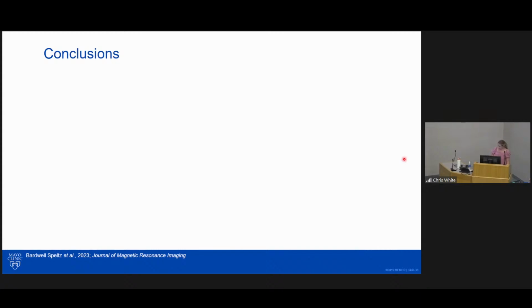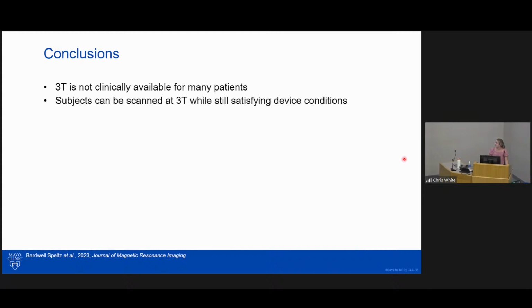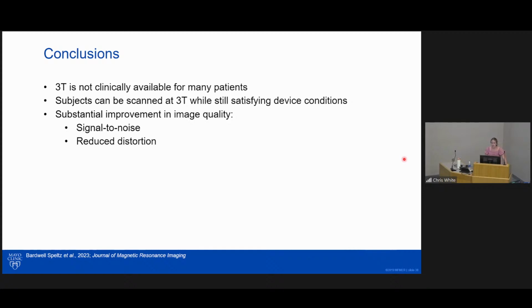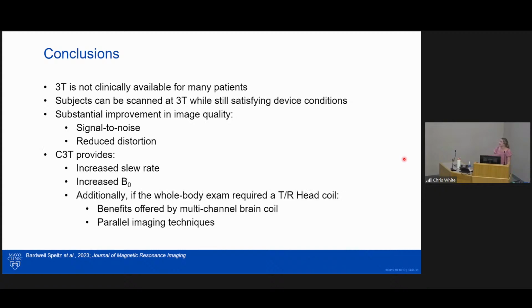So then conclusions. 3T imaging has become the clinical standard for brain imaging, but it is not clinically available for many patients with implanted devices due to MR safety concerns. This study demonstrates how subjects with implanted devices or abandoned CIED leads can be scanned at 3T while still satisfying the device conditions. Compared to the 1.5T whole body scanner, substantial improvement in image quality, such as signal to noise ratio or reduced distortion, was seen on the compact 3T due to various factors, including the increased slew rate and the increased magnetic field strength.